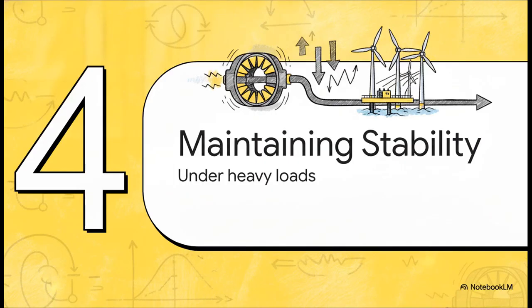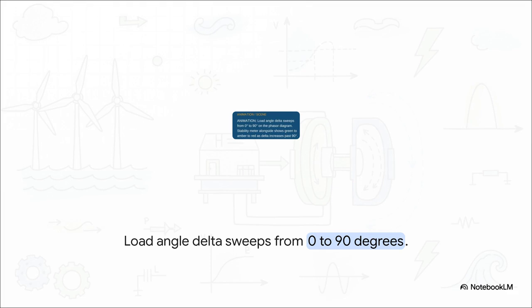All right, on to Section 4, maintaining system stability under heavy loads. Your generator is perfectly happy and stable right up until that load angle delta pushes past 90 degrees. At that exact point, you risk complete and total instability. As demand increases, the rotor essentially advances ahead of the stator's magnetic field. If a sudden, massive load spike pushes that angle past 90 degrees, the magnetic bond physically snaps, the generator slips a pole, and suddenly you're facing a catastrophic, total platform blackout.